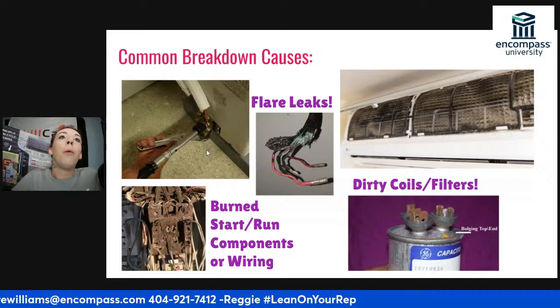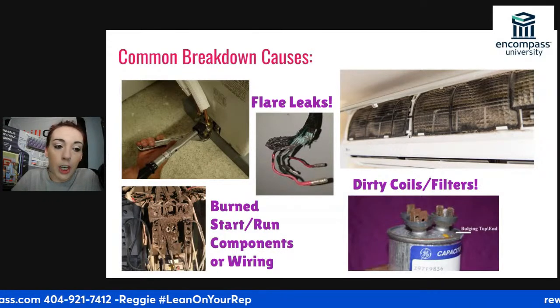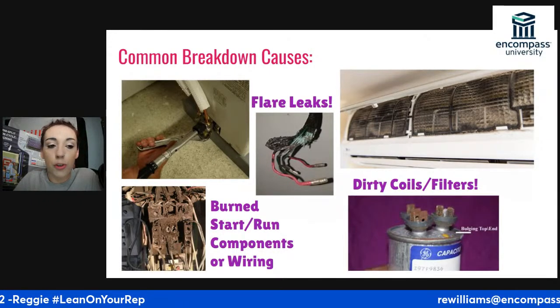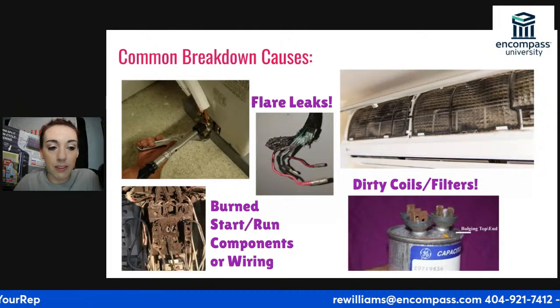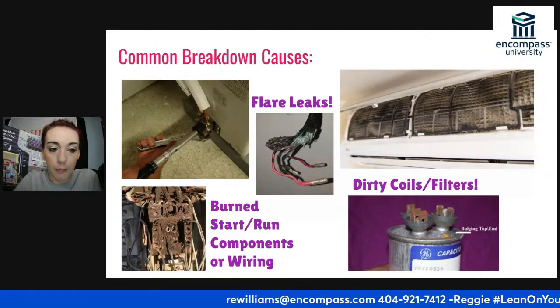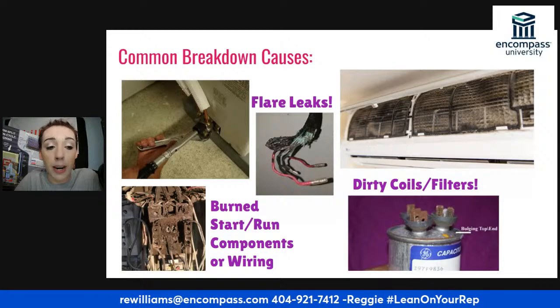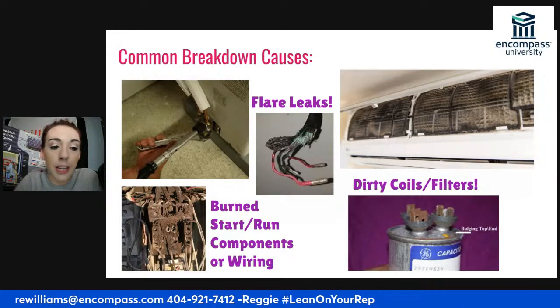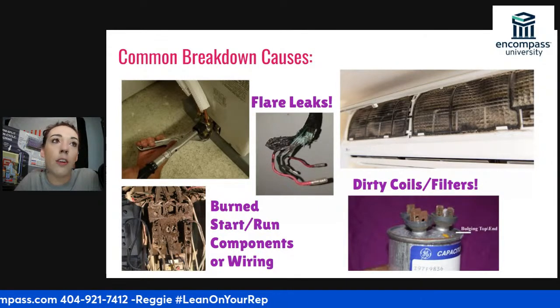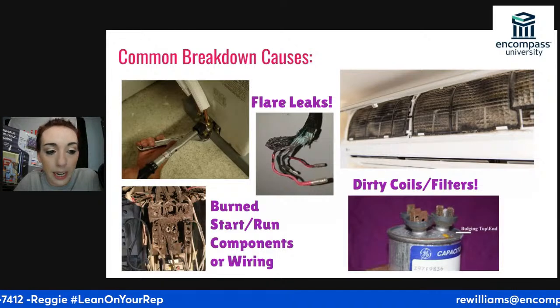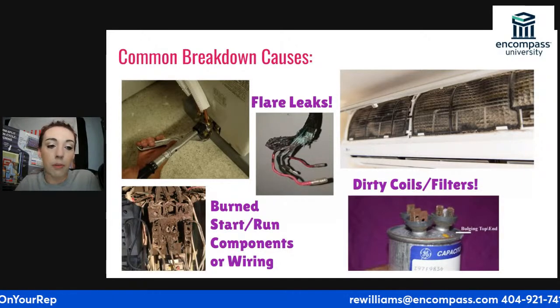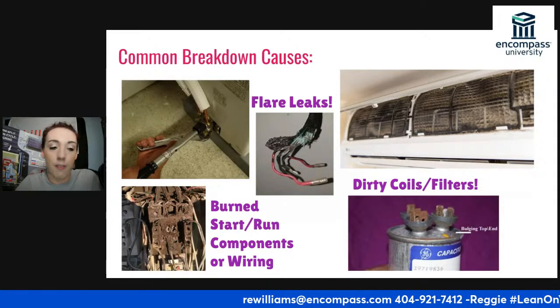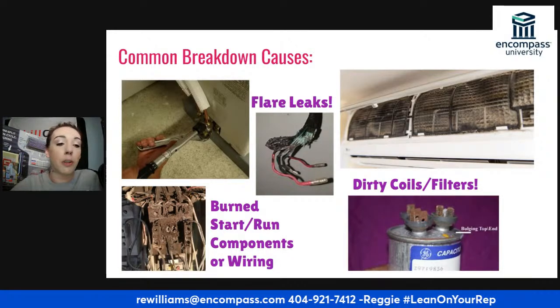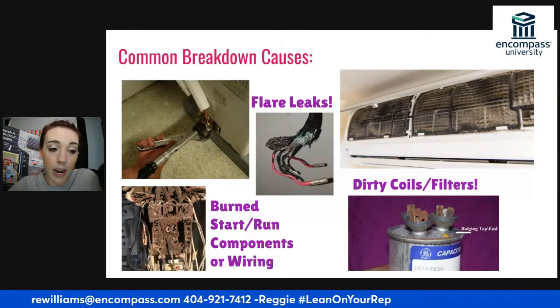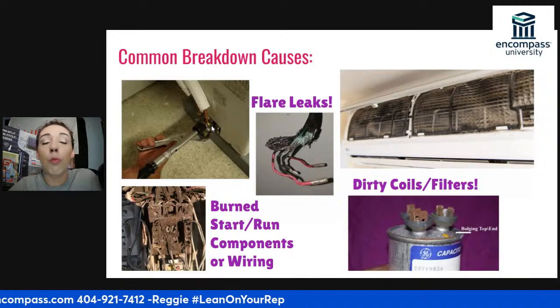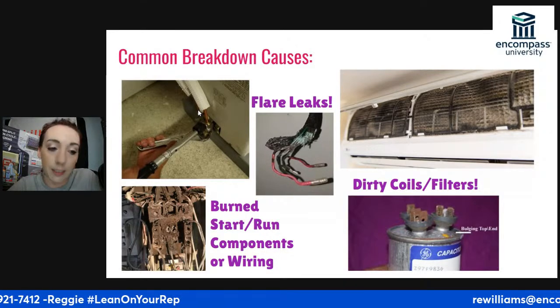So filter dryers are meant, most of you already know, to pull moisture and contaminants from the system after we have installed it. A lot of the reason for the need of that is brazing. Lots of people not purging with nitrogen while they braze, and there's lots of things that can get into the pipe before it's brazed. So we put a filter dryer on that system to help pull that stuff out after vacuum. In mini splits, we don't have a filter dryer, because we have these really clean flare connection line sets.